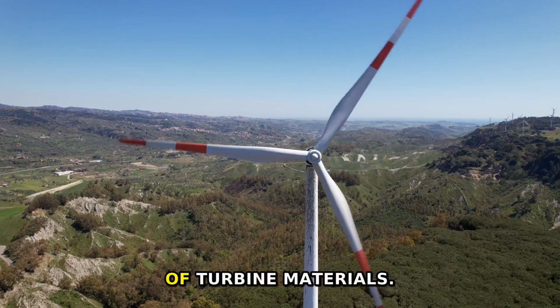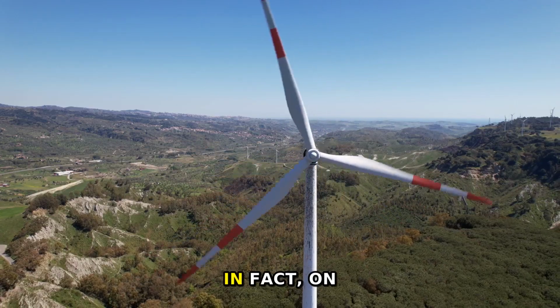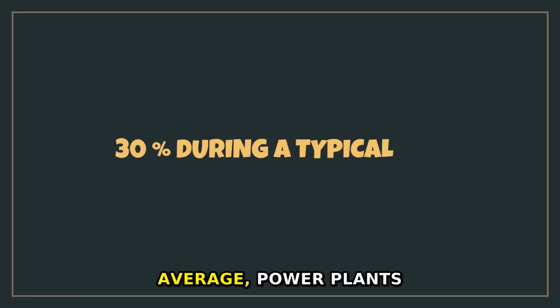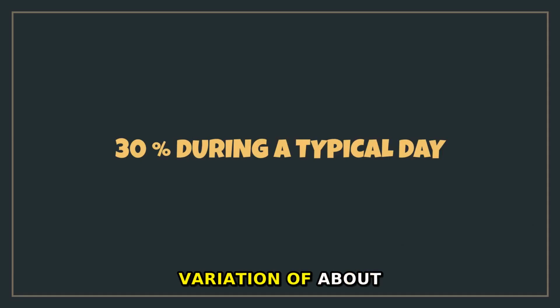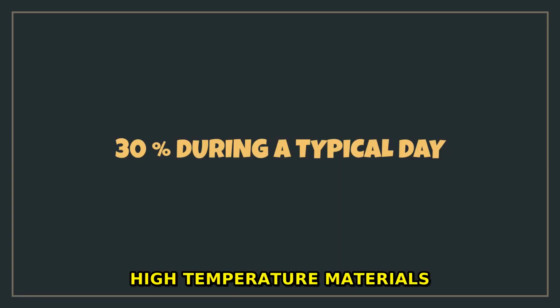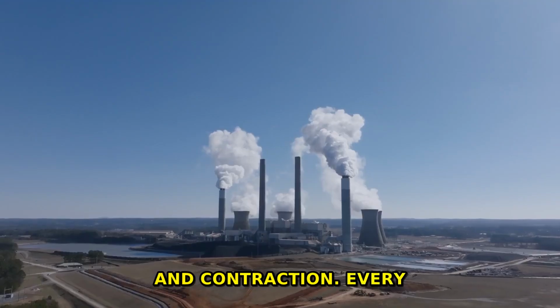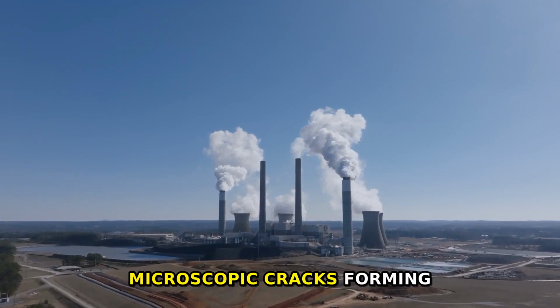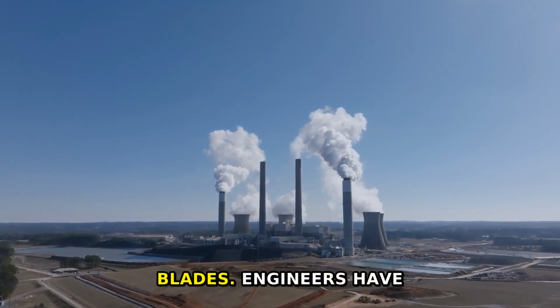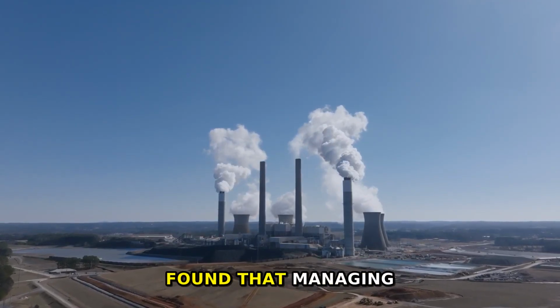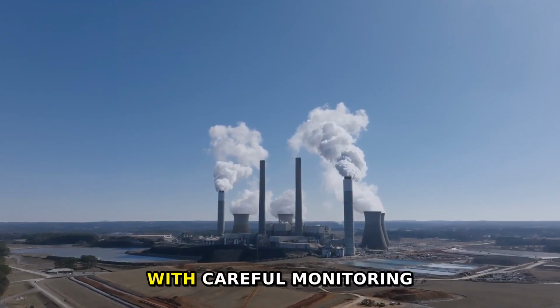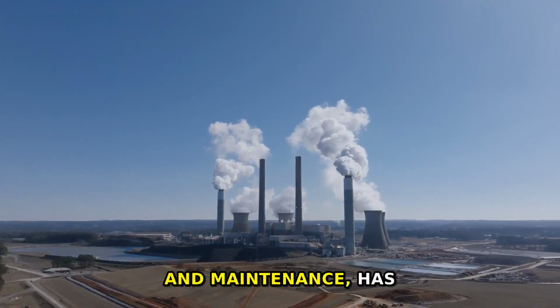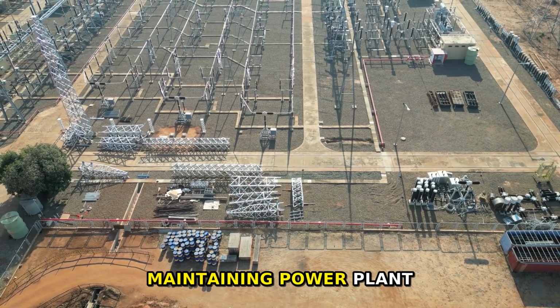Moreover, the phenomenon of thermal cycling, where machinery goes through frequent heating and cooling processes, drastically affects the wear and lifespan of turbine materials. In fact, on average, power plants operate with load variation of about 30% during a typical day. High-temperature materials face fatigue due to repeated expansion and contraction. Every cycle contributes to microscopic cracks forming within the turbine blades. Engineers have found that managing this thermal cycling, with careful monitoring and maintenance, has become integral to maintaining power plant functionality.